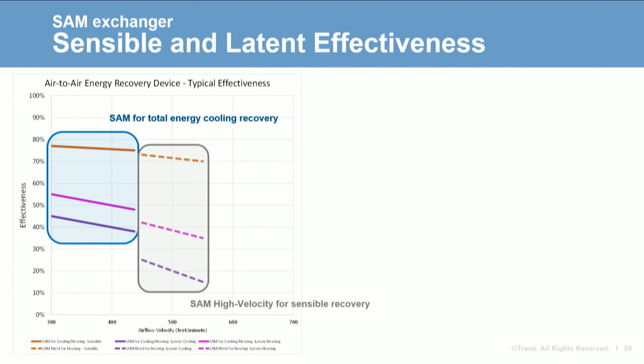SAM is also available with a wide-spacing exchanger for use at higher air velocity, sized for applications at 450 to 550 feet per minute air handler velocity. This high air velocity version is used for winter heating since latent recovery in summer will be very low, but using maximum spacing avoids the need to oversize the air handler. The advantage of this SAM over a sensible fixed plate exchanger is approximately 5% higher sensible effectiveness for the same size, and more importantly, it helps avoid condensate and ice formation.